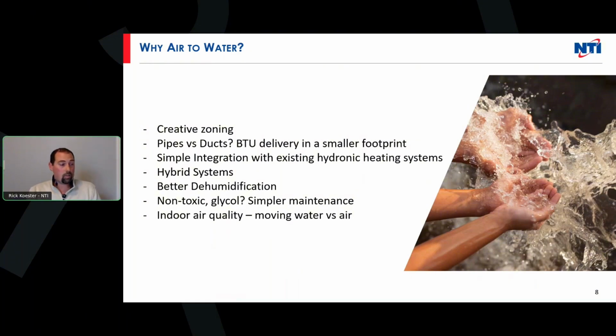Better dehumidification, 100% with water over refrigerant. Water itself, non-toxic glycol, that's the most we're going to have to deal with when it comes to water quality on an air-to-water system. And that really is the maintenance. The maintenance is making sure we have the right amount of glycol, making sure it's not corrosive, and maybe having some inhibitors if there are metallic parts in our system. So that's more of the focus on maintenance.